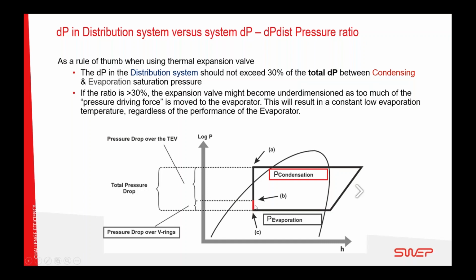What we do with our distribution system is to steal a part of the pressure drop over the expansion valve and put it in our distribution system to hold back the gas. We have noted that if we steal more than 30% of this, and you're using a thermal expansion valve, the expansion valve can start to lose its grip, can start to lose its control. If you're using an electronic expansion valve, SWEP can steal much more of this pressure difference, but it depends on what kind of expansion valve you have. So that's why we normally say maximum 30%.